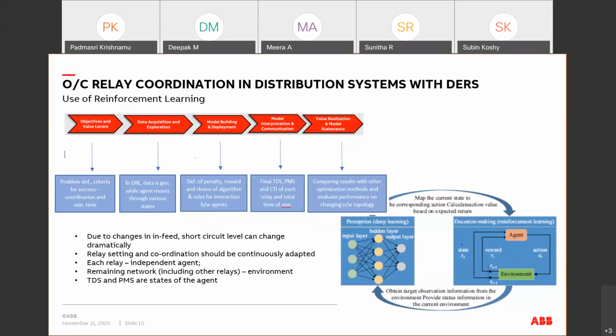So here what we are doing is, we will consider each of the relays as an independent agent. And when you consider one relay, all the other parts of the network, including the other relays, become the environment for that specific agent. The state of the agent is its own present TDS and PMS setting, and the current time of operation of its backup or tertiary relay. So that will become the state.